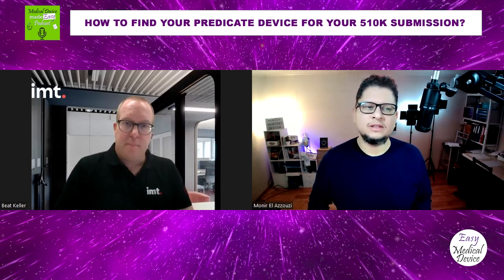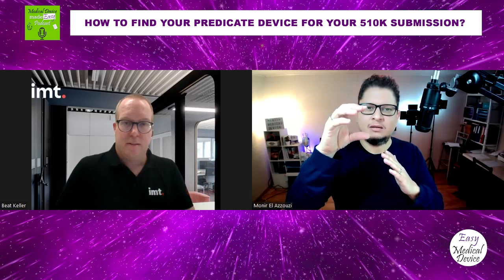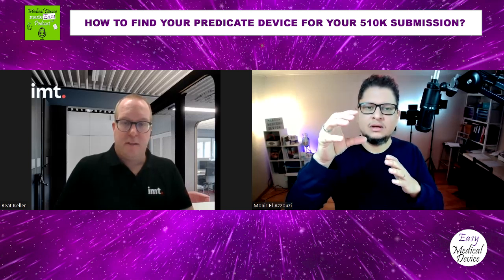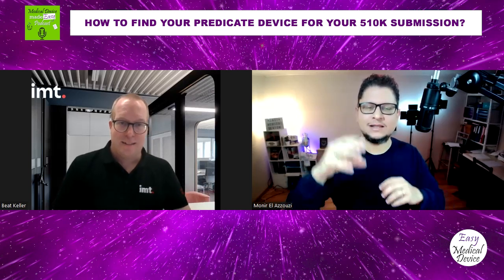So one thing that is important to understand here is that it's like a pyramid, if I can say. So the first one that was on the market maybe went through a PMA, for example, or through a de novo. Then the second one will compare himself to the first one. The third one will compare himself to the second one, etc. So it's like this kind of thing. So as you've said, maybe 3 years after, the last one is comparing himself maybe to the first one at the beginning. But if the first one was made 20 years ago, maybe he should go to another one that is more recent and using more the same kind of standard.